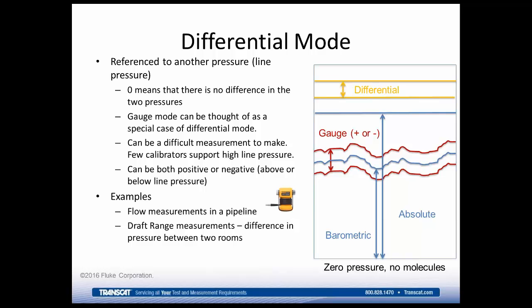One of the key examples of that is a line pressure, where it's referenced to a much higher pressure, which is like what we see up here, where you've got these two yellow lines. The bottom line can be thought of as the line pressure, and the differential measurement is just how far different we are from that line pressure. So 0 means that there's no difference in the two pressures, whereas a positive pressure means that your test pressure is slightly higher, and a negative would mean that your test pressure is slightly lower than your line pressure.